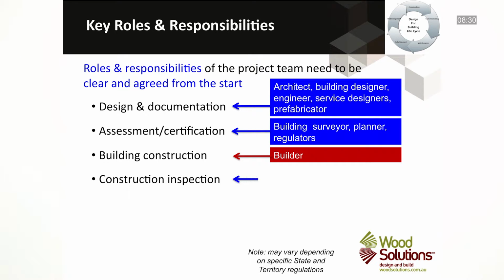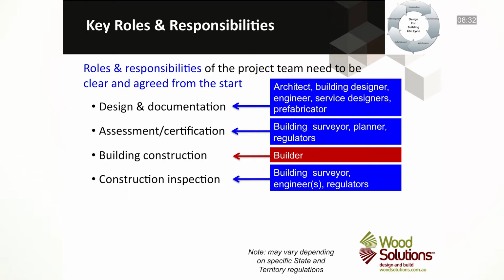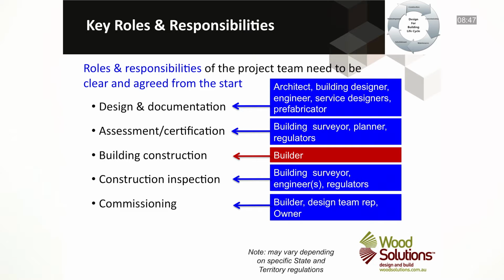Inspection of the construction works will fall to the responsible building surveyor, or perhaps the engineer, depending on the element being inspected. It is again paramount that all critical building construction elements be inspected to ensure compliance and signed off accordingly. With commissioning, which may happen progressively and then a final commission, this is the responsibility of the builder and the senior project team representative to ensure that the project is completed as per the design and functioning appropriately.